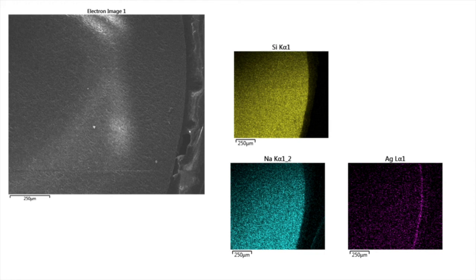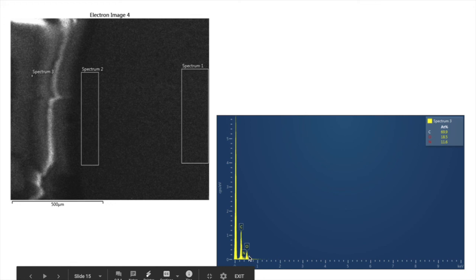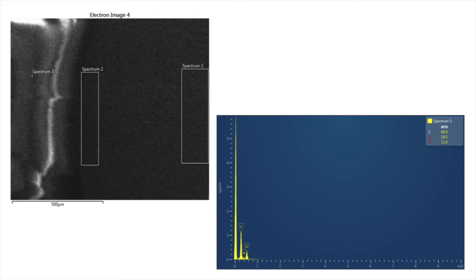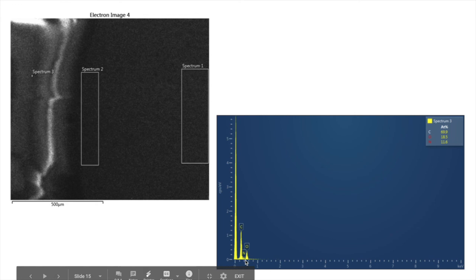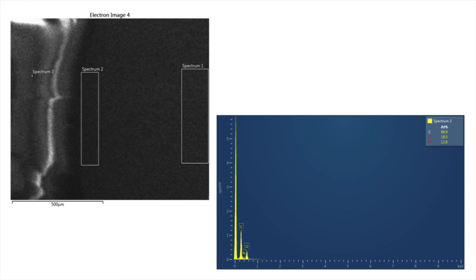You might have also noticed that some of the lower intensity elements are quite low. EDS has trouble picking up those low amounts because their intensity is so small compared to the background. And so oftentimes when we're dealing with low concentrations, so less than one weight percent, you really need to have either much longer dwell times to get that signal increased, or you need to have other techniques that are better with trace level elements. We're actually going to talk about some of those techniques later in the semester.